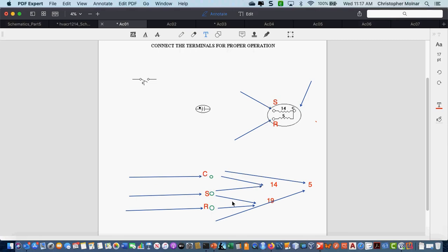It all has to do with the math. When you take a resistance reading from start to run, you're going through both windings, so the numbers are going to add up for your total. So again, if you get a motor that's not wired and you have 3 leads sitting there, you can always find out by using your ohm meter what start, run, and common is.